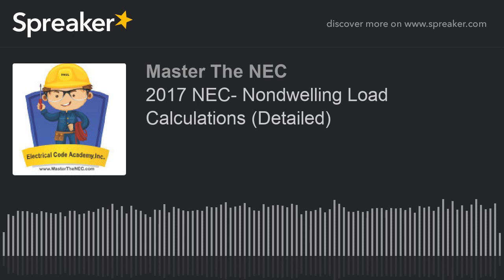And the other thing to remember is if we were dealing with over 800 amperes and we were paralleling, the cumulative total of circular mills and the ampacity values of the total sets have to be equivalent or greater than the rating of the overcurrent device if we're over 800 amps. Again, under 800, we've got next size rules that we can utilize. Over 800, we really don't have that luxury, and we have to make sure that our conductors are sized to handle fully whatever the rating is of the overcurrent device. Those are the general rules that we want to follow, and we'll leave it simply at that.